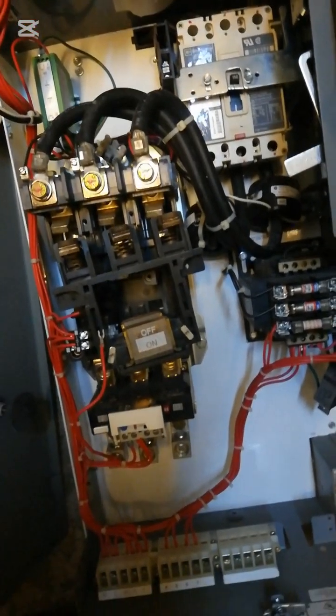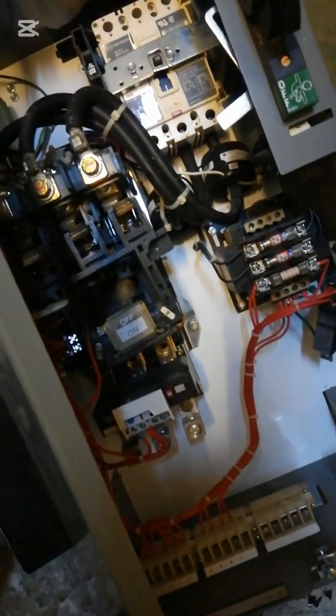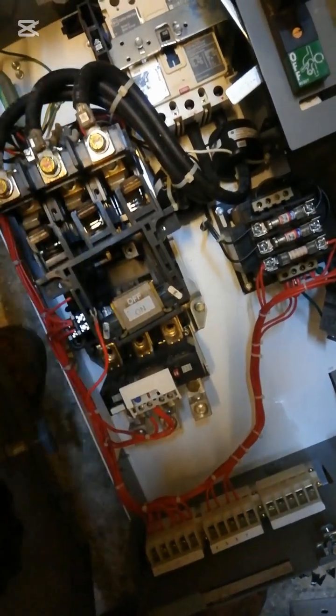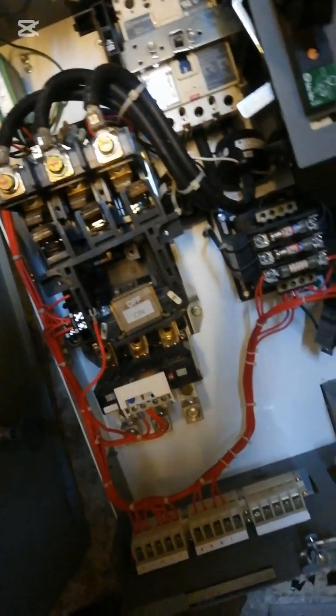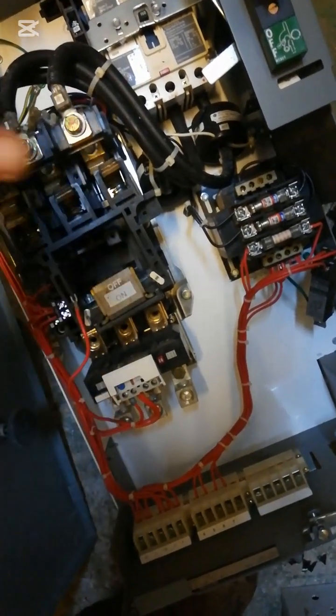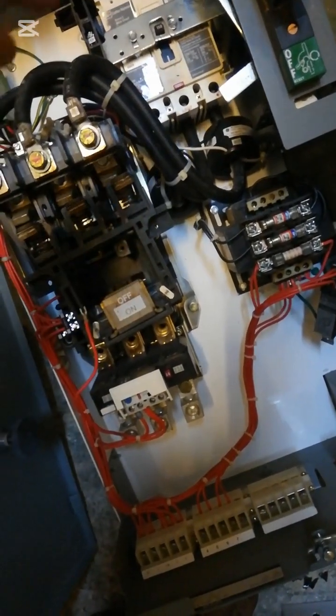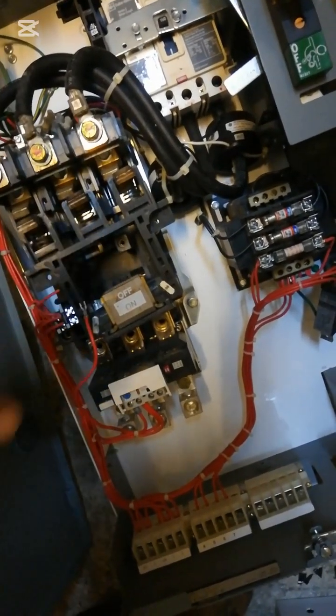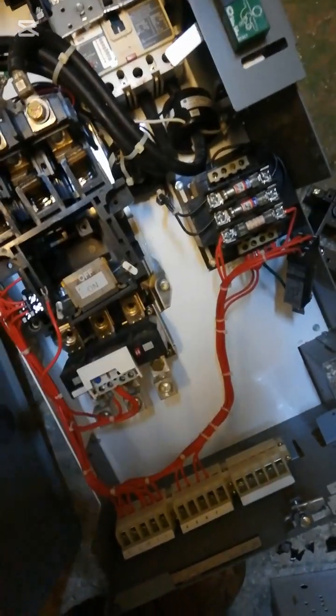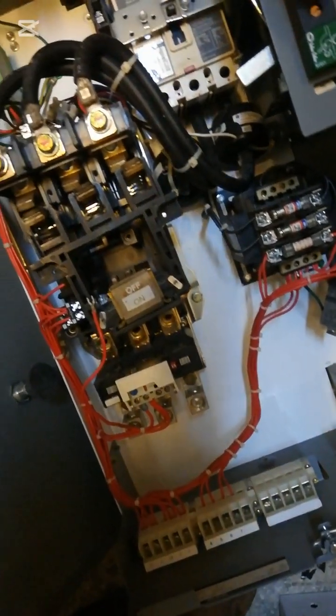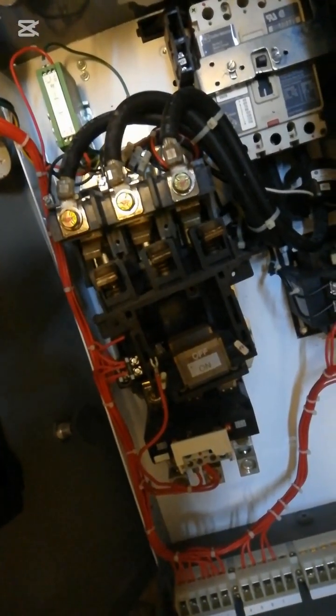Right? And again, this is called an Allen Bradley starter, typical, right? We usually use the term bucket because this is what consists of the whole control circuit: starter, breaker, or should I say the contactor, the breaker, transformer, overload section. And this is like a current transformer that can be used now to connect to the analog, right? That you can know what current is going through.